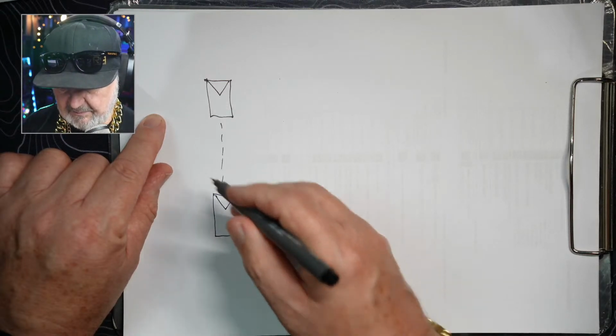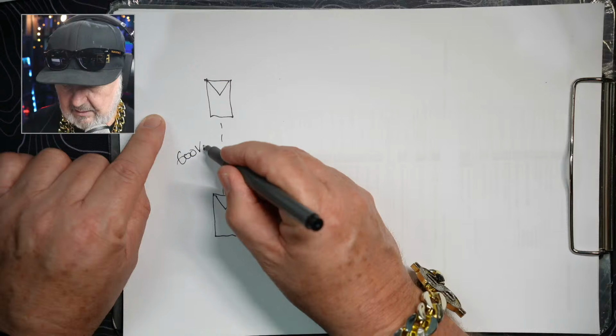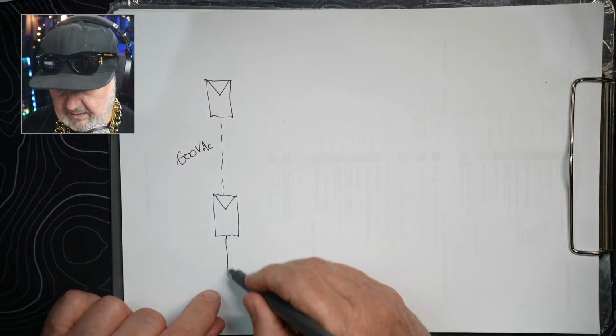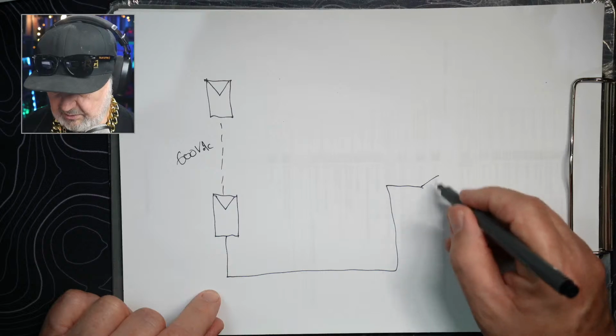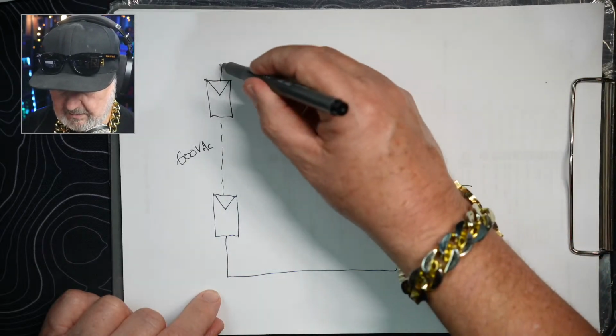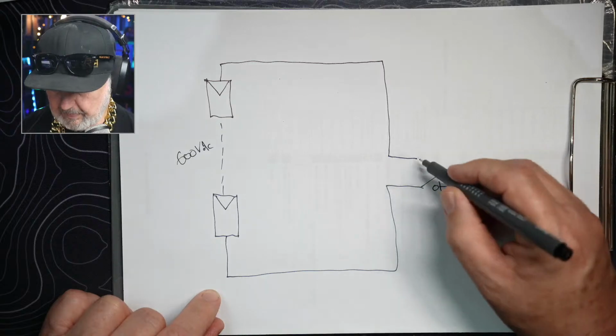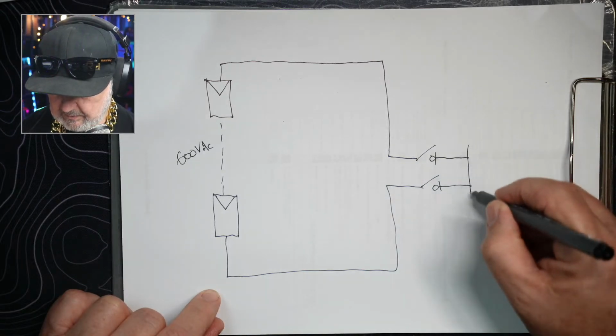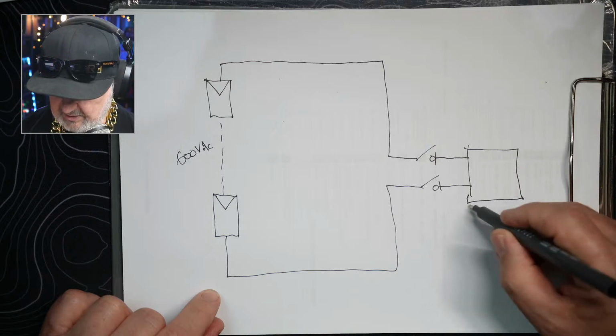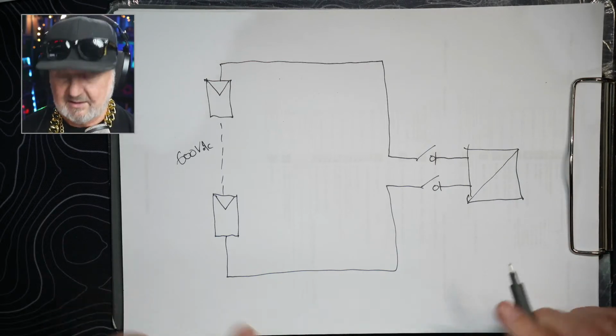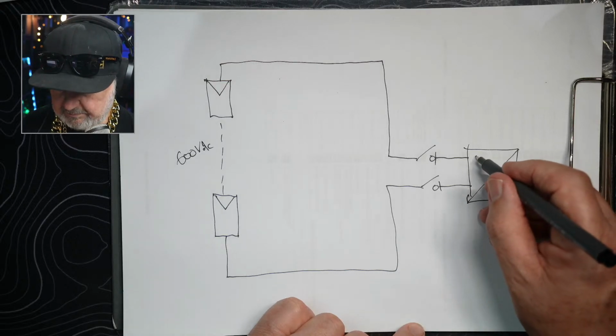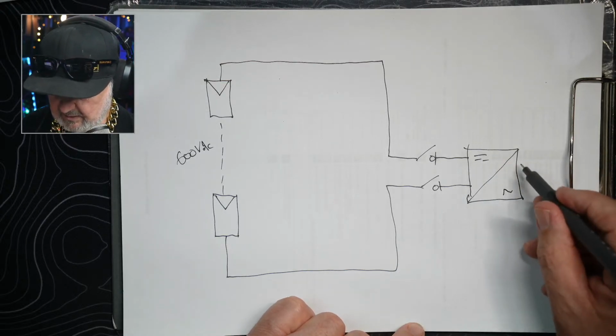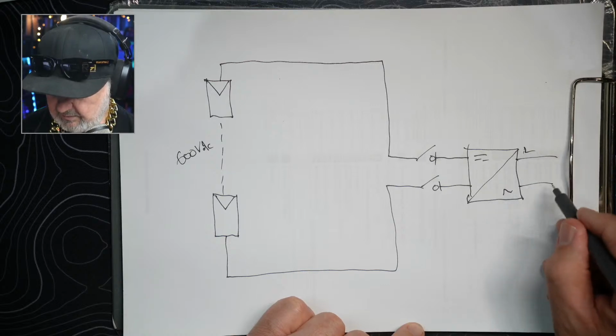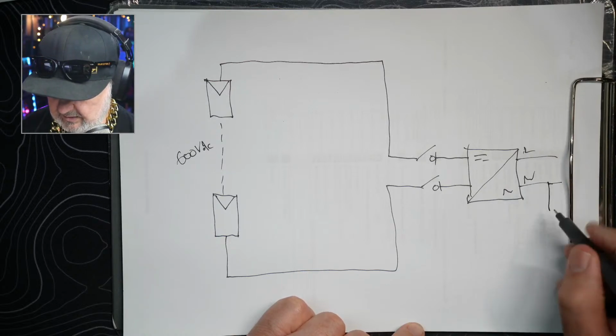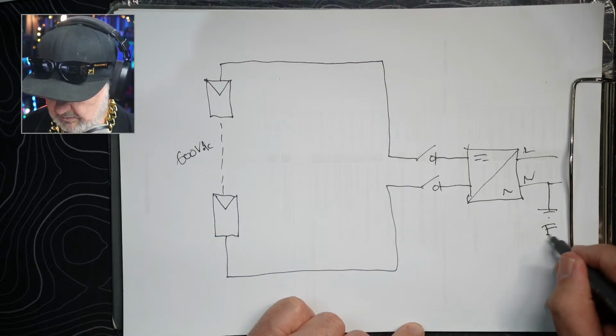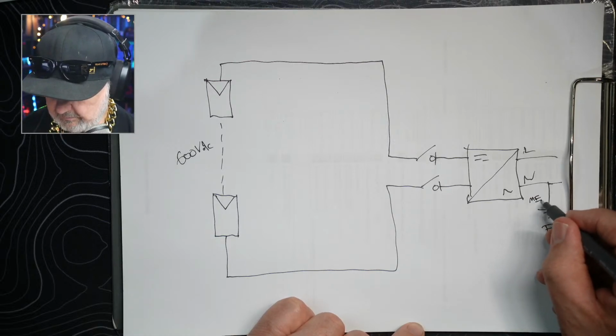And so there's our, let's say, 600 volt DC PV array, and it's connected to our PCE. And the PCE is non-separated. So the symbol for non-separated is just a single line. Double line means separated. So we've got our DC and our AC, and then of course we've got live, neutral. We'll have an MEN as our earth, so that's our MEN.